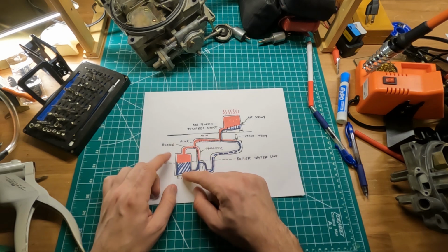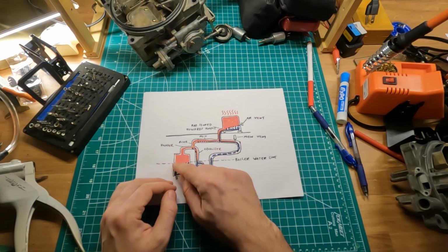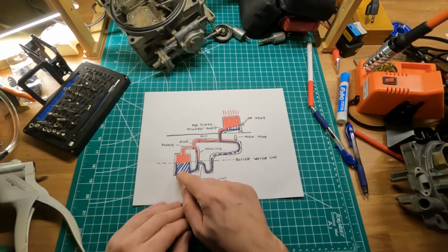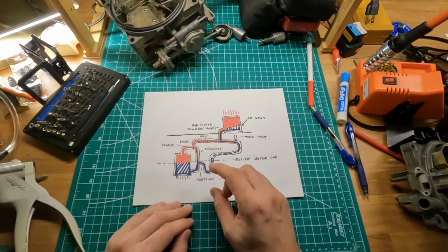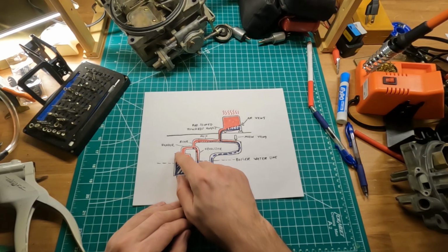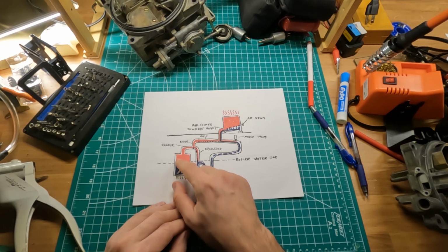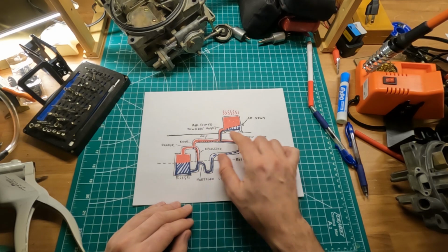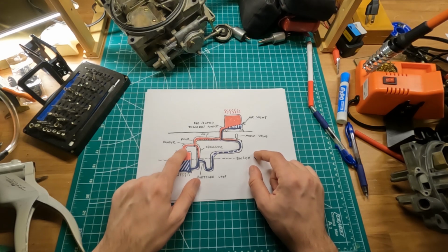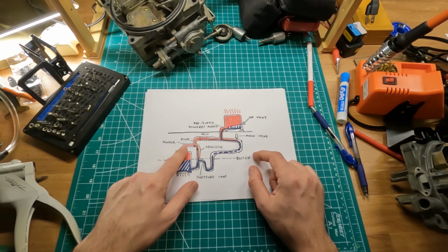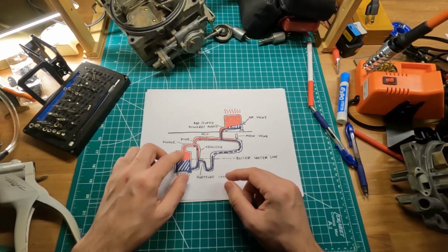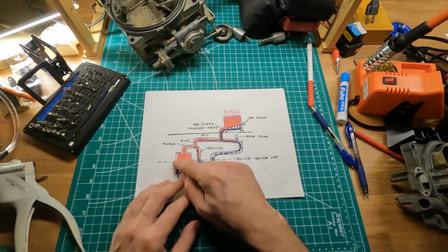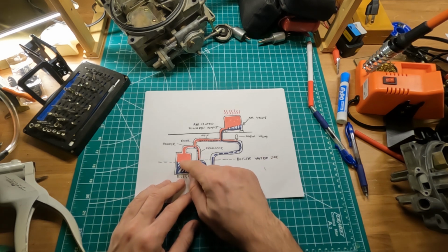So here we have a boiler. A boiler is basically a vessel with some water inside, and the moment you apply some heat to that water, by definition that water turns into steam. The boiler has some kind of pipe attached to it, so the steam can be directed via this pipe to enter all the elements of the system. The very pipe coming out of the boiler is called the header. The purpose of the header is to slow down the steam velocity, and also to allow it to cool off a little bit as the steam is rising.